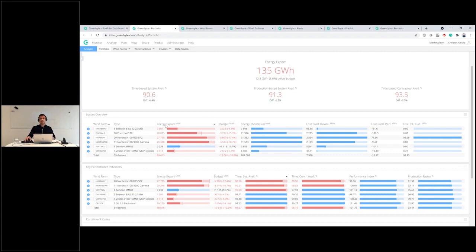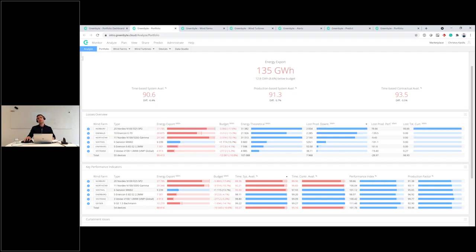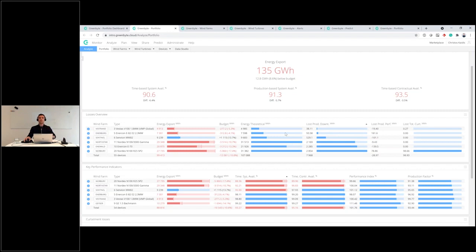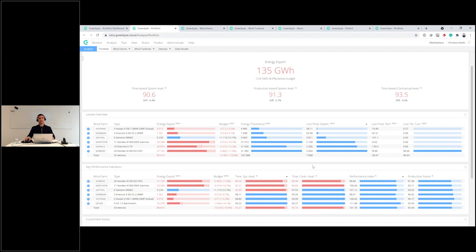The gap between the theoretical ideal and the actual energy export is allocated to lost production due to downtime, lost production due to performance, and lost production due to curtailment or external interventions. By sorting on those KPIs we can focus on a specific asset to investigate further — either by looking at KPIs in absolute lost megawatt-hour fashion, or in a normalized fashion like time-based availability or performance index.